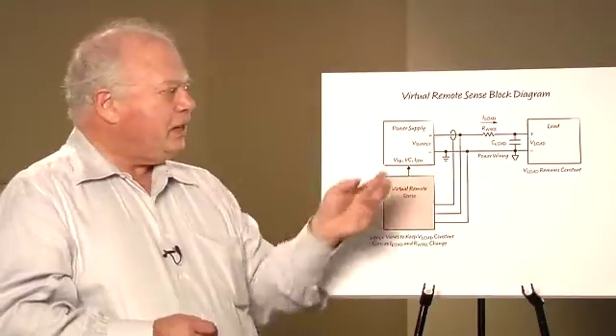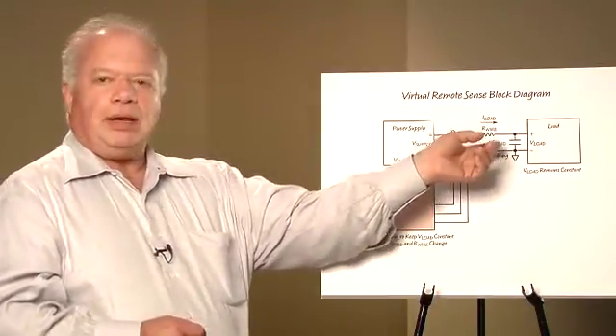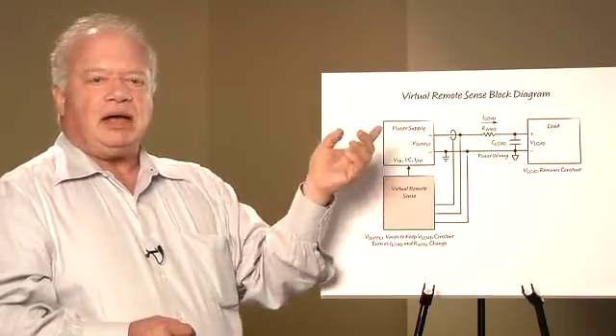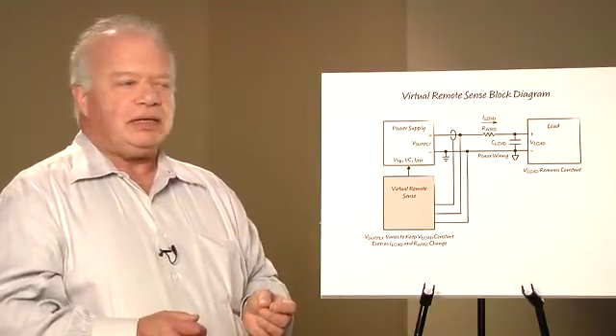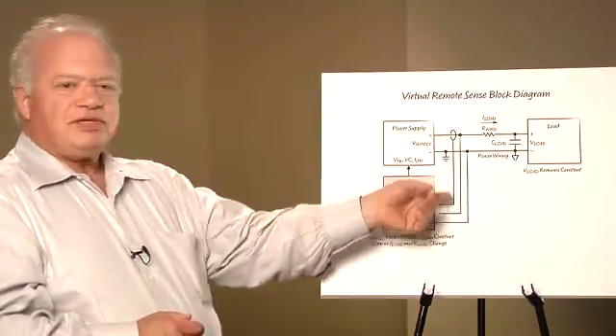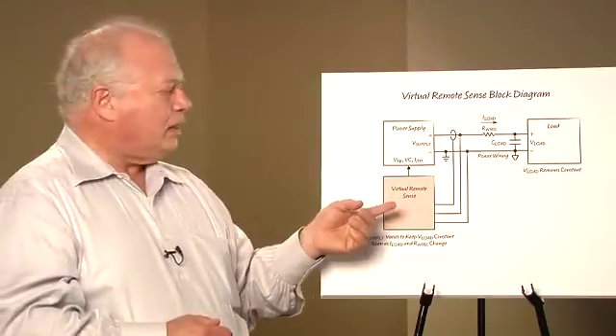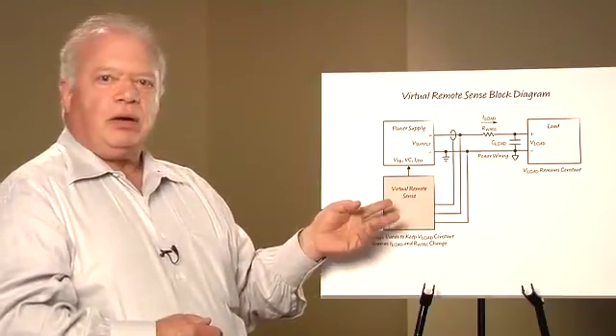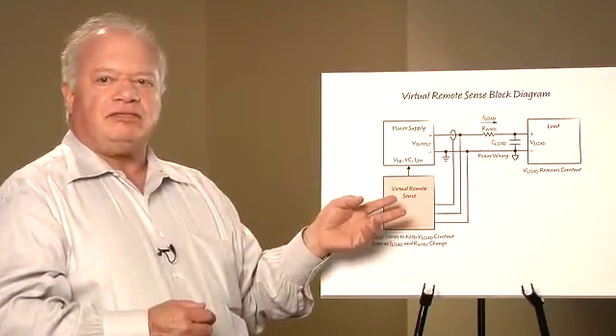The way we do that, the magic part, is we interrogate what the line resistance is at a pretty high frequency, anywhere between a few hundred hertz and eight kilohertz. We have several sample and holds in the 4180 that hold voltages and currents at different times.